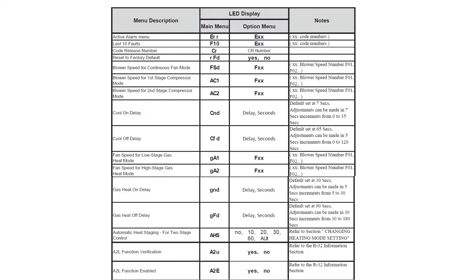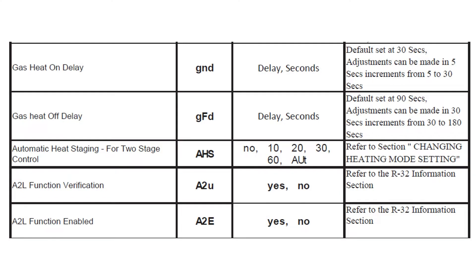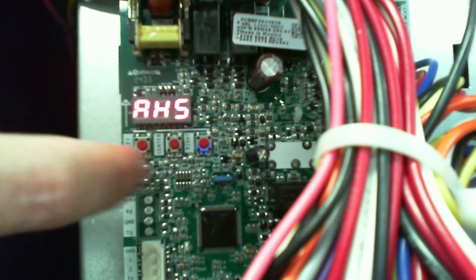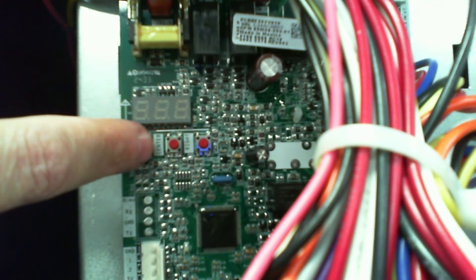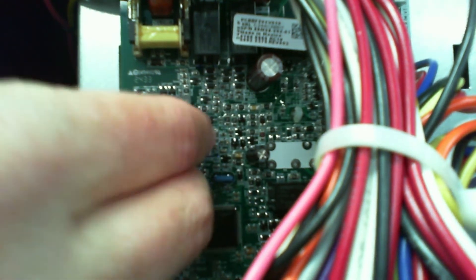The next question we get is about AHS — automatic heat staging. It ships from the factory in the 'no' position, so you have a W1 and a W2 and it's looking for a two-stage stat. If we scroll down to AHS and hit the center button, we'll see 'no,' meaning no automatic time settings. If we're not going to use a two-stage stat, we can scroll left to right and see 'automatic' — 60 minutes, 30 minutes, 20 minutes, or 10 minutes. 'Automatic' will try its best to hit the 20-minute mark, starting sooner or later. In this case we'll hit 'no' and hit the center button twice.